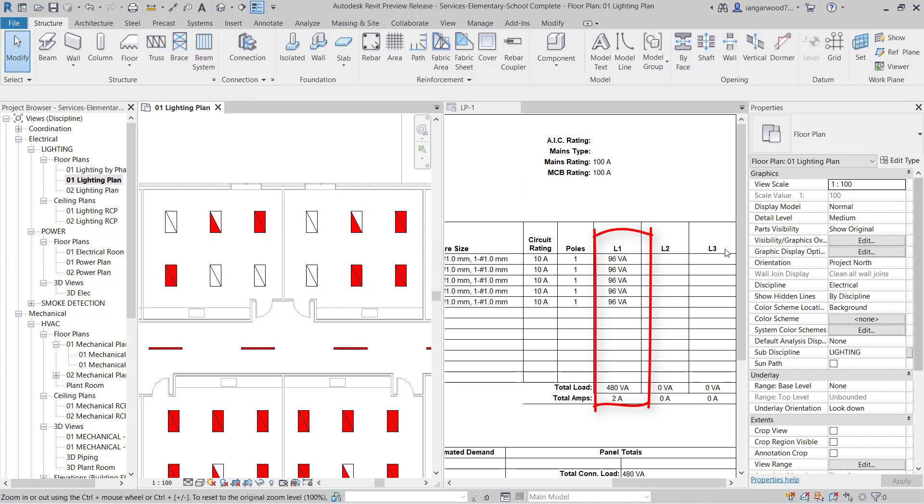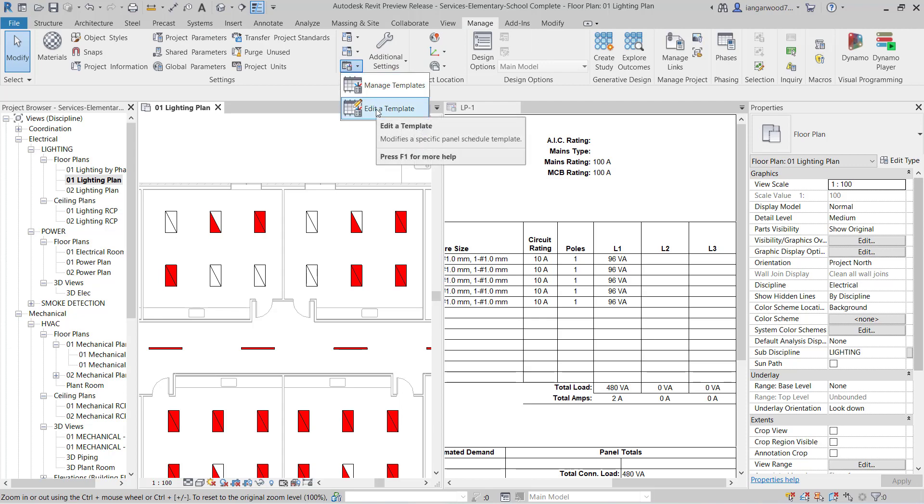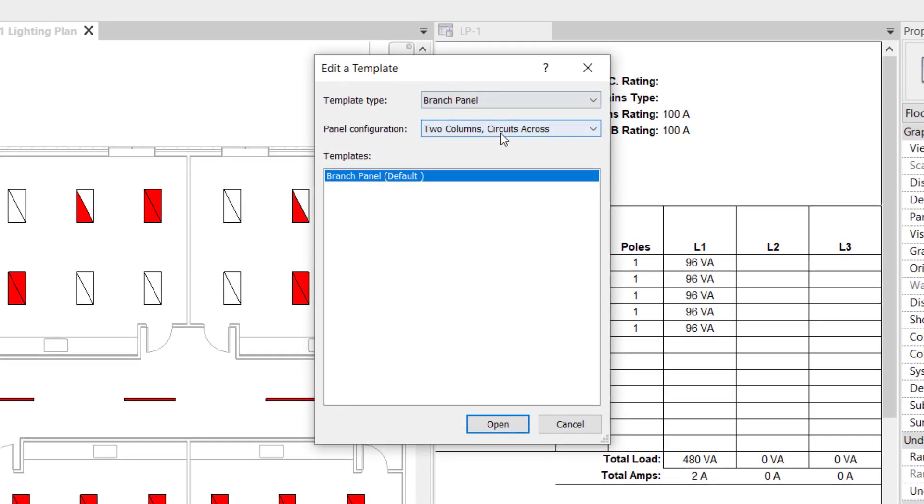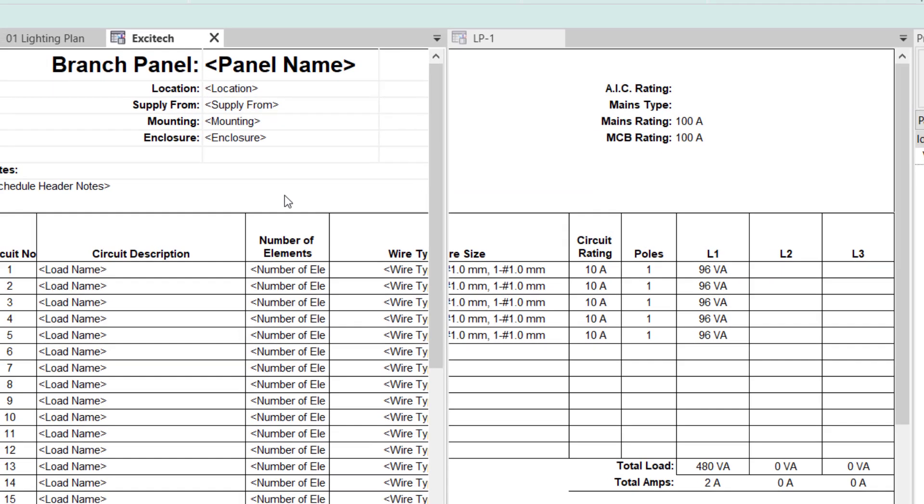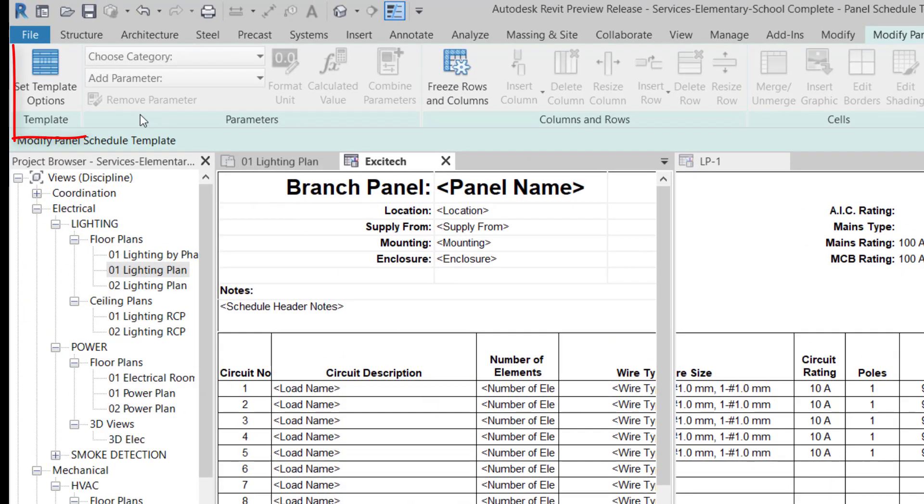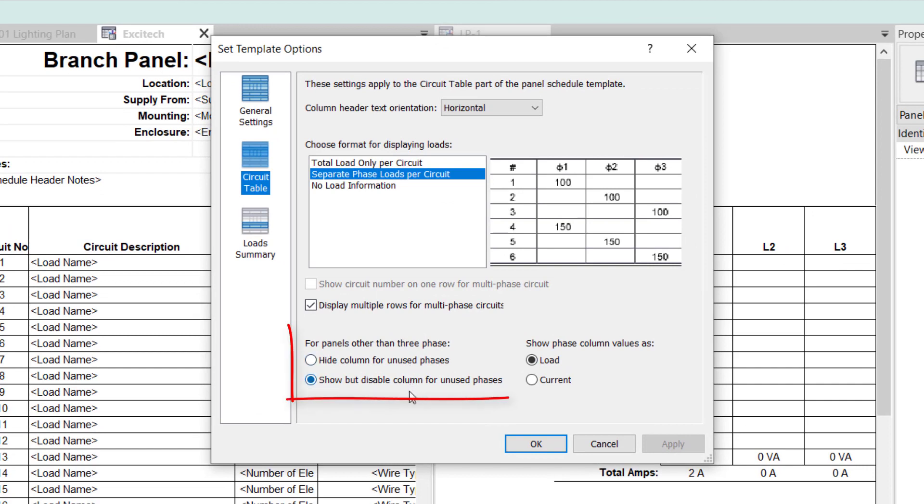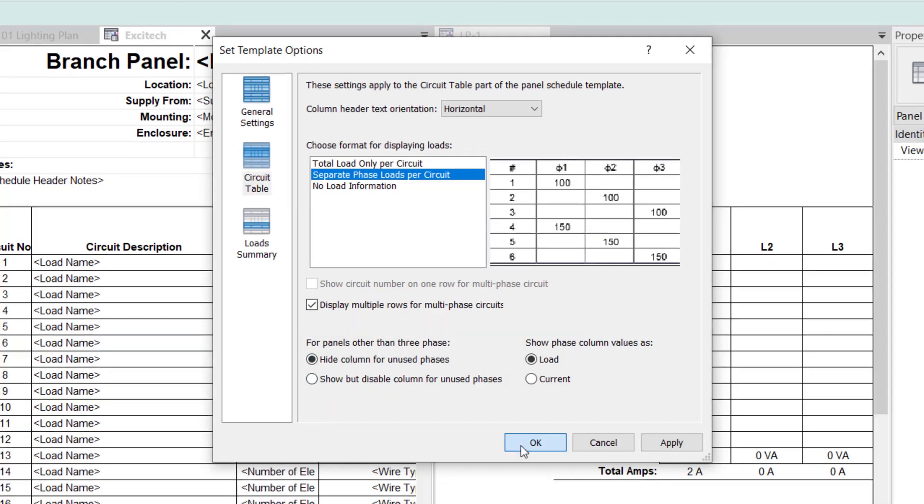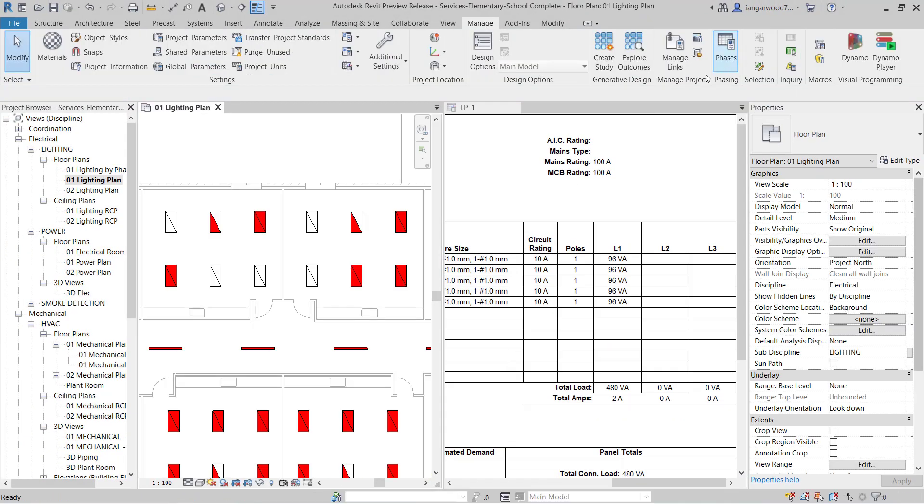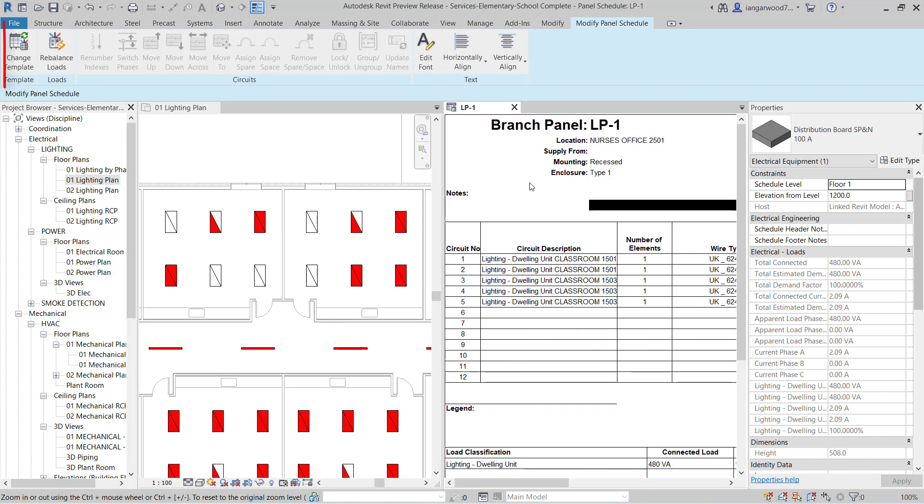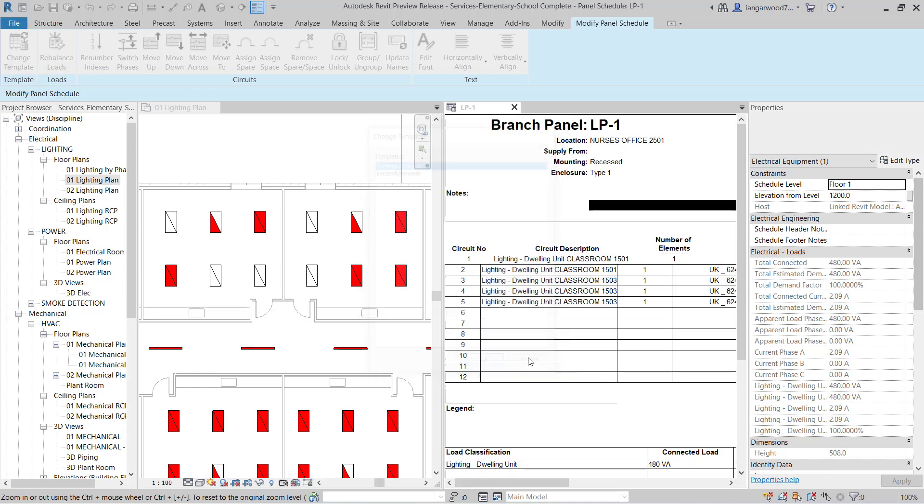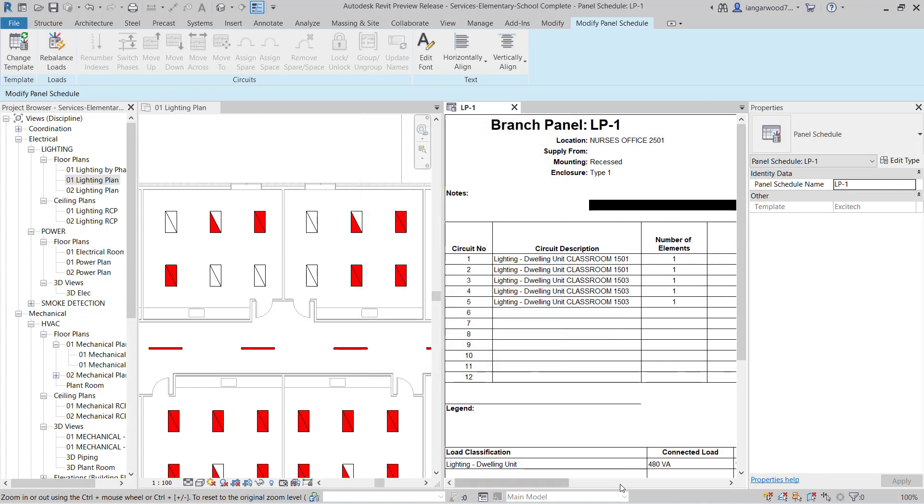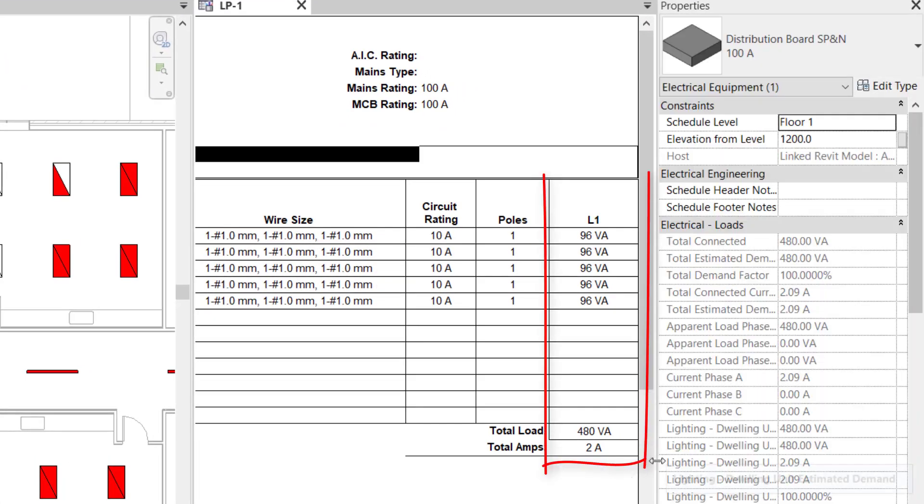The second issue we found with single-phase circuits was that of dealing with the unused phases. To see how this has been addressed in Revit MEP 2021, we need to edit the template and take a look at the template options for the panel schedule. Here, we will see a fundamental change in the way unused phases are dealt with. Revit MEP 2021 now allows all unused phases to be disabled or hidden rather than just the third phase. After making the necessary adjustments to the template and choosing to hide the columns of unused phases, we can then apply those changes and update the panel schedule in our project. A look at the final panel schedule shows only a single column with all loads connected to the same phase.